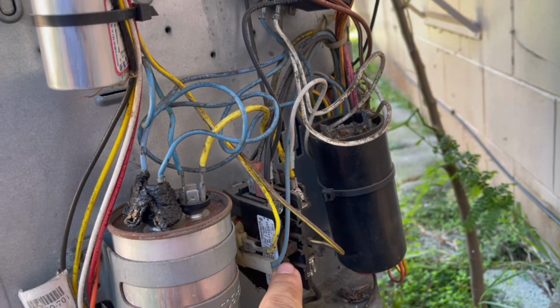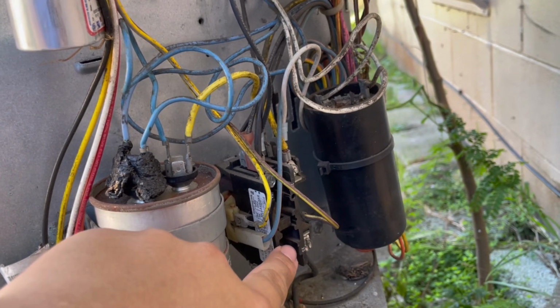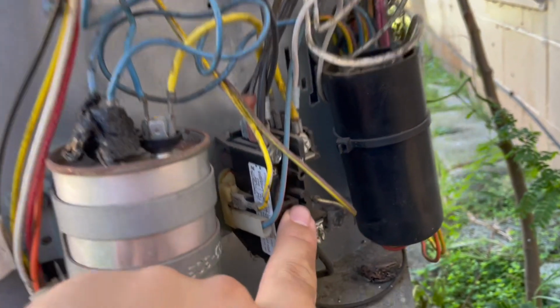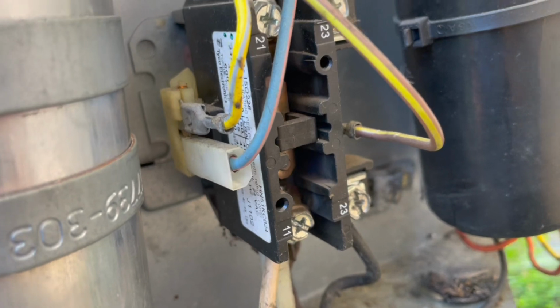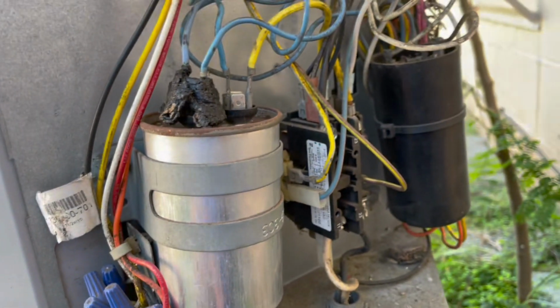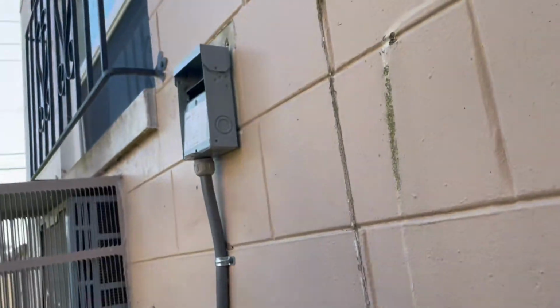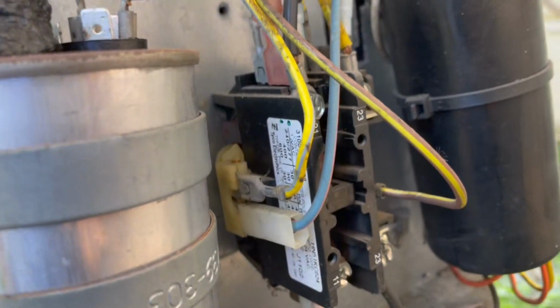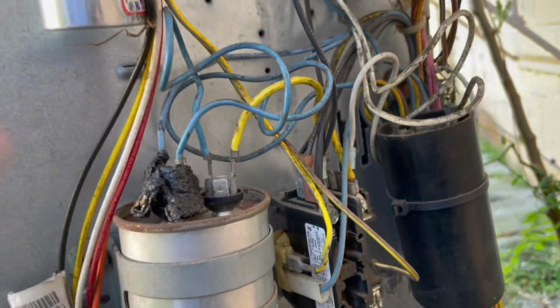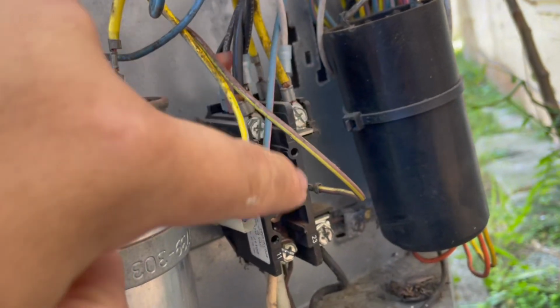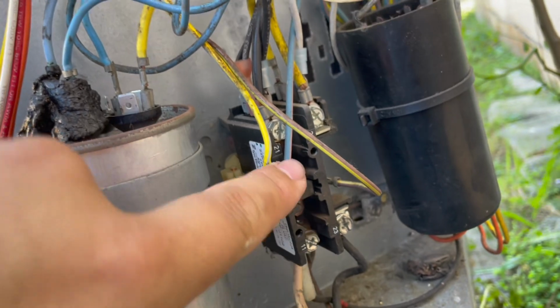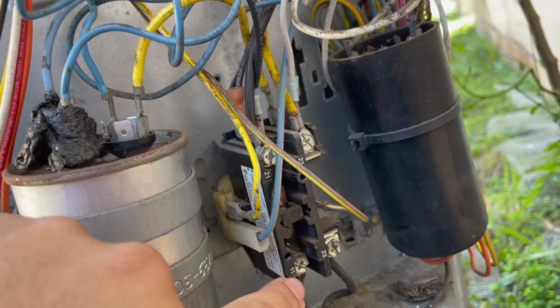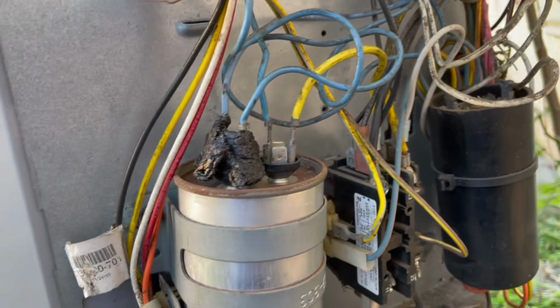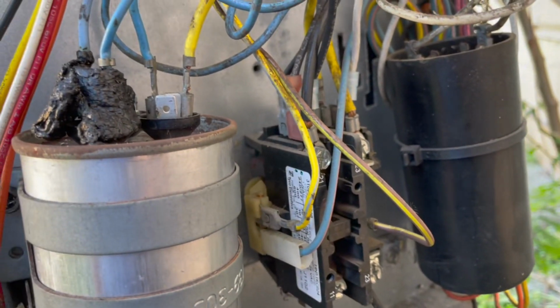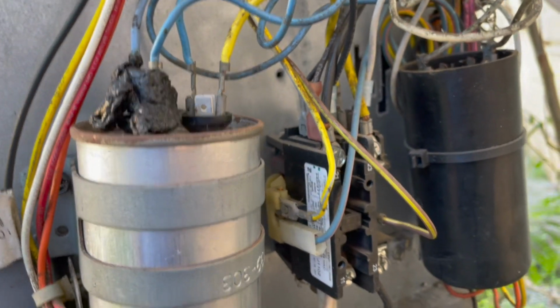Right now, the current issue the customer has is the contactor here. The contacts, I guess, look like they're melted shut. I've got no low voltage, no high voltage. It's disconnected right now, but it's still pulled down. Even when I've got the disconnect in and high voltage running to the unit, I get no power across the contacts here, so nothing runs. So I'm gonna put a new contactor in here for him, and then we'll see what happens.